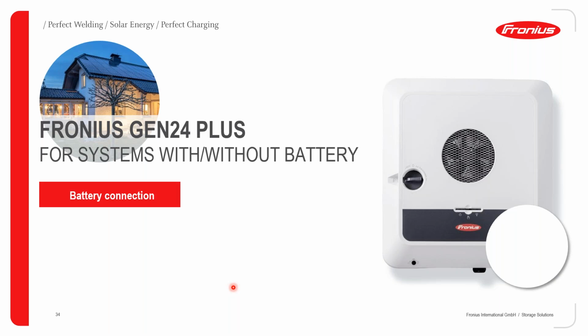Another important point to take home about the Fronius Gen 24 Plus is the fact that it's a battery inverter. So you can use this inverter with a battery, but this inverter can also be operated without a battery system, and therefore work like a typical grid-connected system. When you talk about a battery connection, we have two battery types that have been qualified from two manufacturers for use with the Gen 24 Plus inverters. One of the manufacturers is BYD. And for this one, we have two variants, the HVS and the HVM.